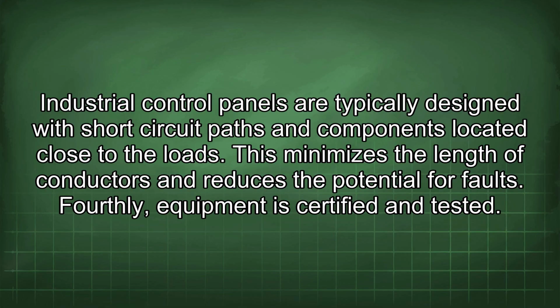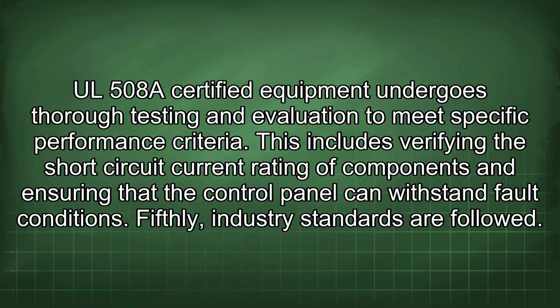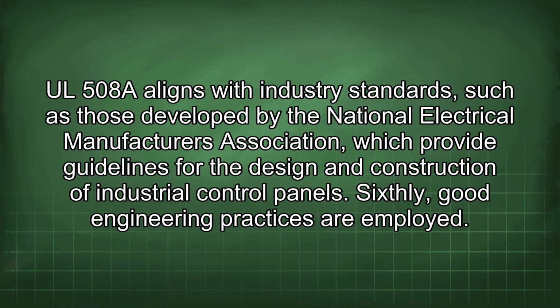Fourthly, equipment is certified and tested. UL 508A certified equipment undergoes thorough testing and evaluation to meet specific performance criteria. This includes verifying the short-circuit current rating of components and ensuring that the control panel can withstand fault conditions. Fifthly, industry standards are followed. UL 508A aligns with industry standards such as those developed by the National Electrical Manufacturers Association, which provide guidelines for the design and construction of industrial control panels.